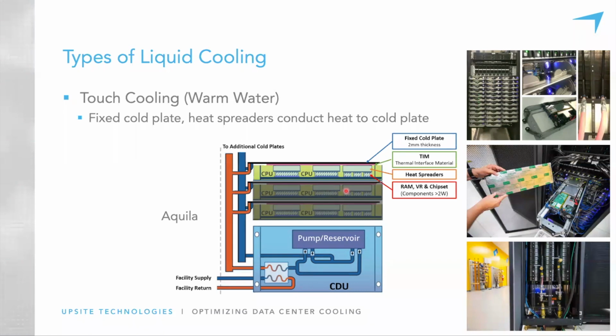The way that it works is each of the power producing components has an aluminum heat spreader that sits on top of it, and the heat conducts through that heat spreader and then through a thermal interface material up against a cold plate with warm water flowing through it, and that removes the heat. Quite warm water can be used, up to around 115 degrees Fahrenheit, 46 degrees Celsius, and still keep the processors at an appropriate operating temperature. So this opens up the possibility of using waste heat.